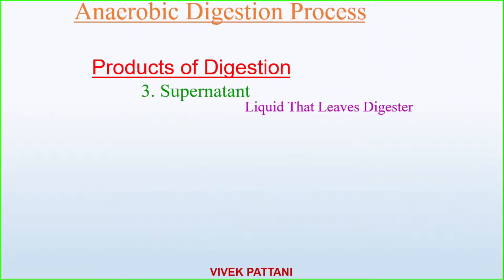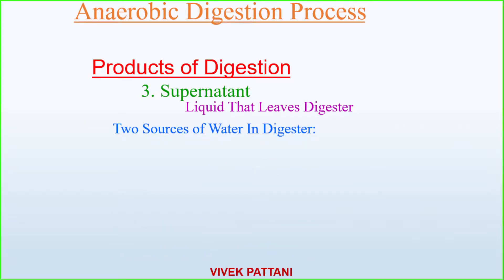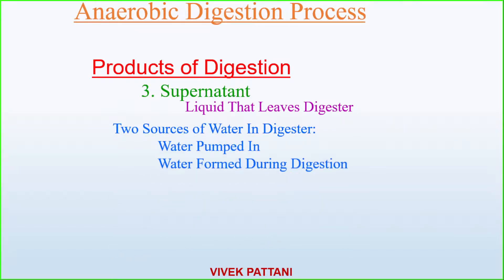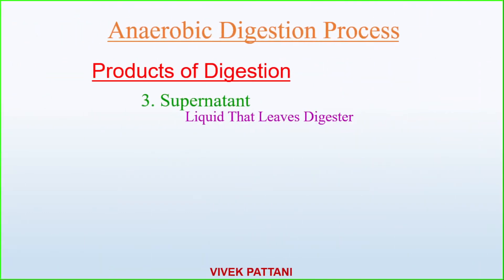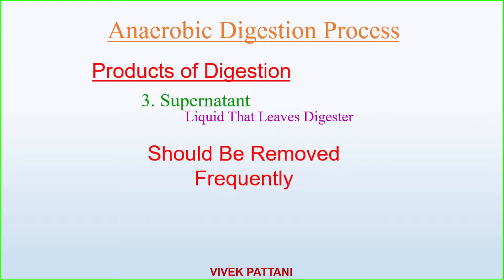The third product is supernatant — the liquid that leaves the digester. It comes from two sources: water pumped in with the sludge and water formed during digestion. It is recycled through the treatment plant and is high in solids, BOD, and ammonia. Supernatant liquid that leaves the digester should be removed frequently in small quantities.